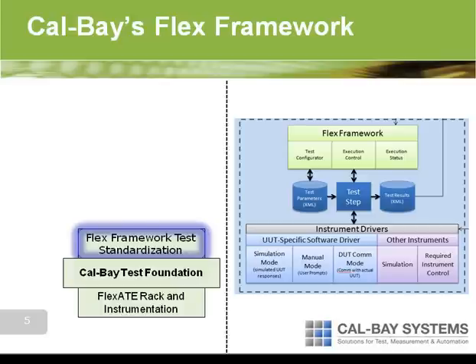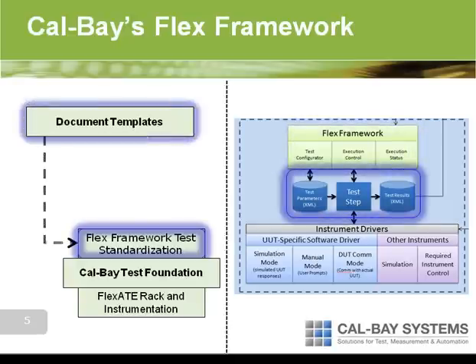Taking a closer look at the Flex Framework, we see 3 core areas handled. These are standardized processes for test configuration, execution control, and execution status. Every ATE will handle these components in the same way. We have defined templates and a process to ensure that all stakeholder requirements are properly documented and seamlessly integrated into software. These documents rigorously define the custom ATE components such as test step software, test script configurations, and test results. The Flex Framework has 2 flavors, one which is open source and LabVIEW only, and a second which leverages TestStand. Our test results are written in a defined XML schema, which can be automatically pulled into tools such as Interstage.